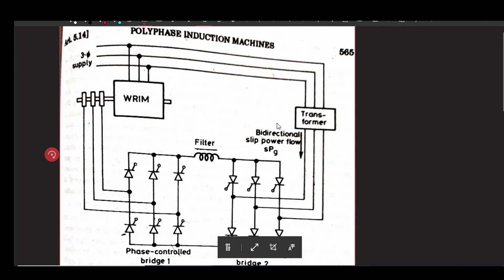Another thing you can do is drive it at super synchronous speed. Here, you just change the angles of these thyristors and push power into the rotor at a frequency of sF. Then the rotor will get power, and that power will push the rotor ahead of our synchronous speed.